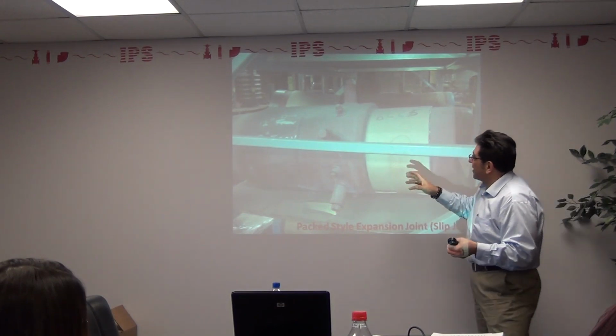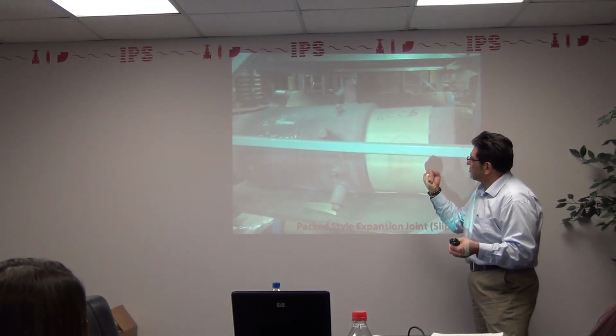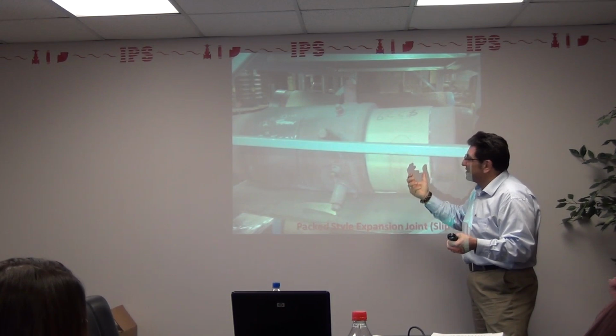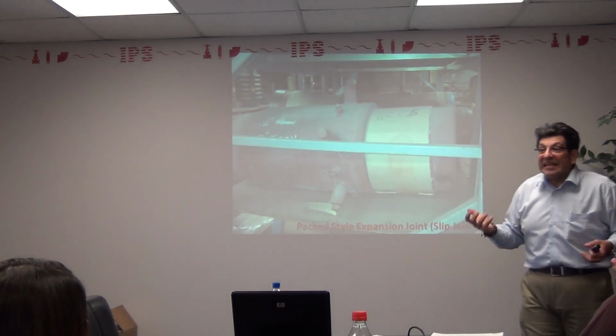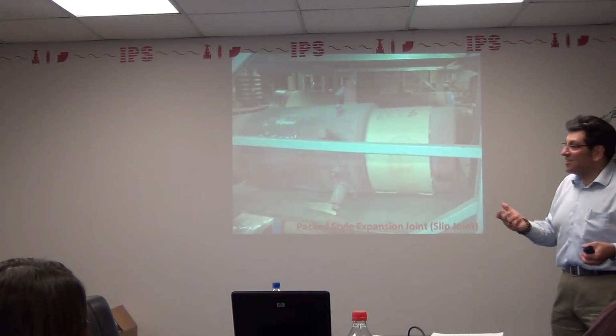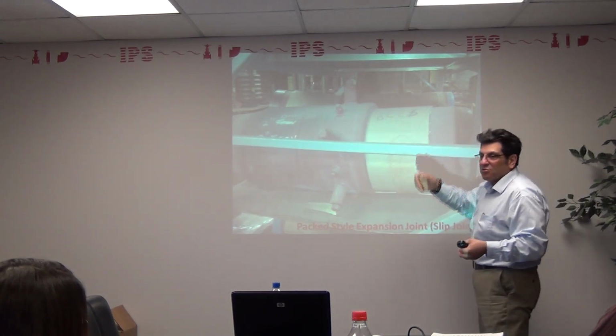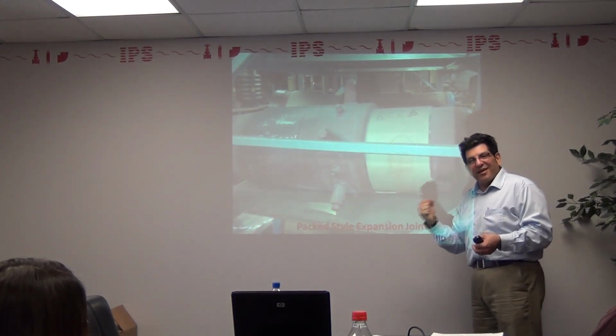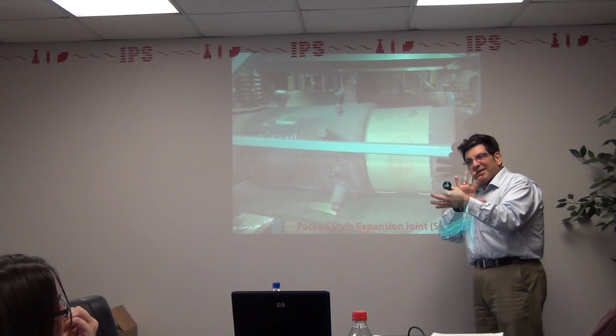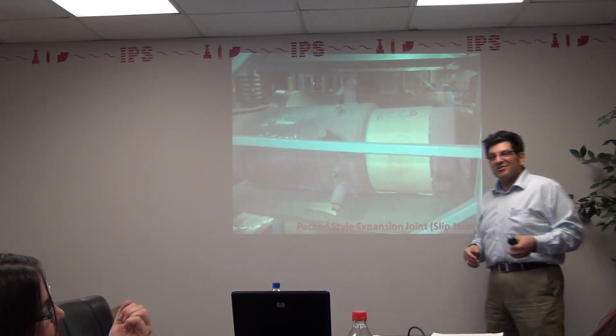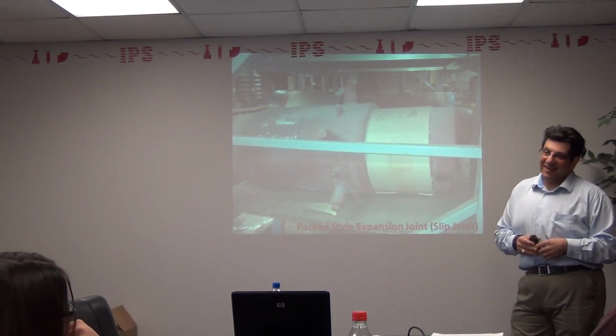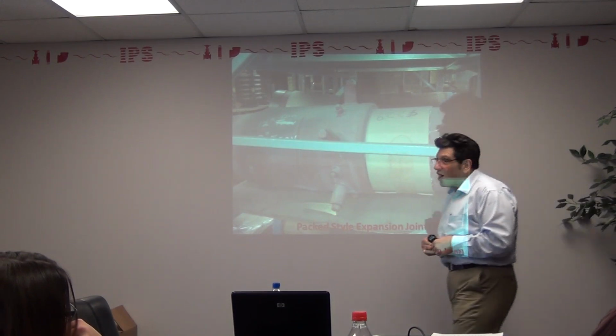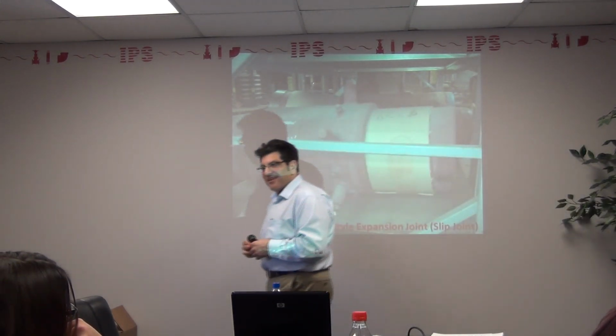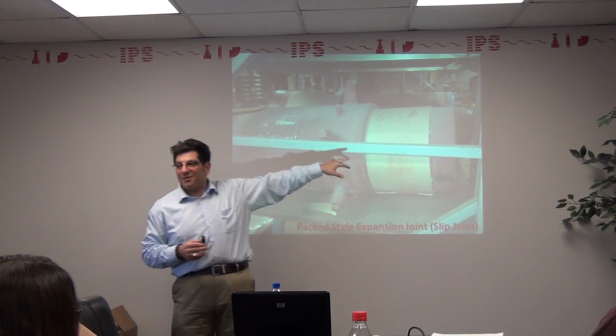In order for packing to work right, it has to be saturated with whatever the media is, and it has to weep, so it has to leak. There's a gland here, so if it's leaking too much, you go down there and crank on the nuts to make the packing expand more so it doesn't leak as much. But how often do you think a maintenance guy is going to go into a tunnel, a confined space, and tighten the packing?